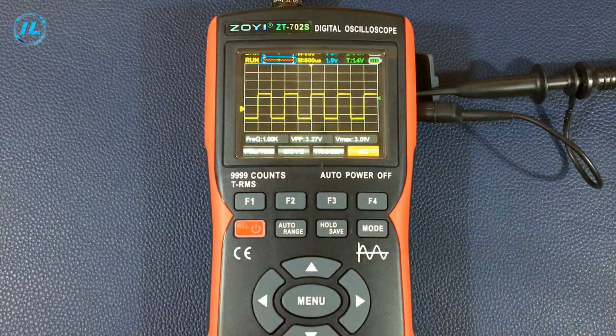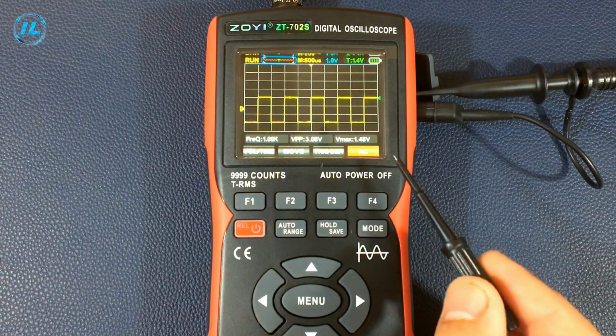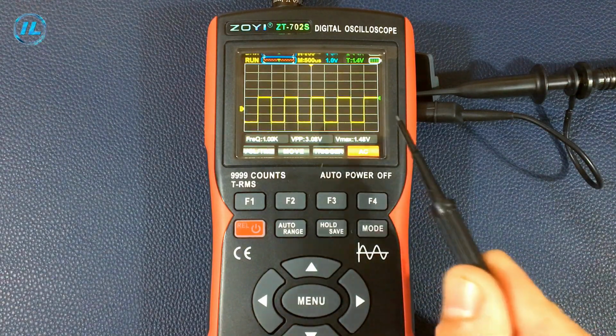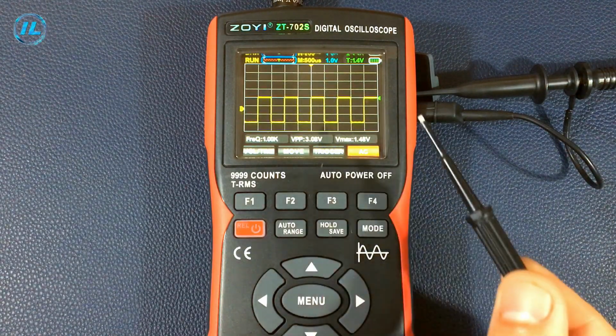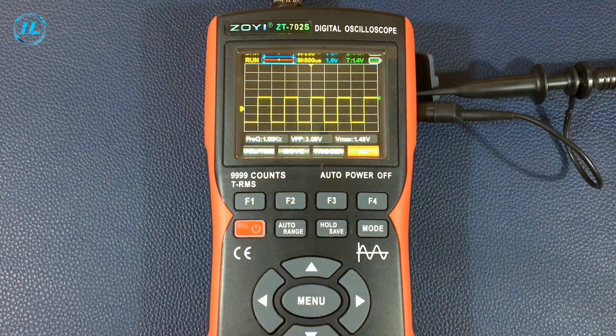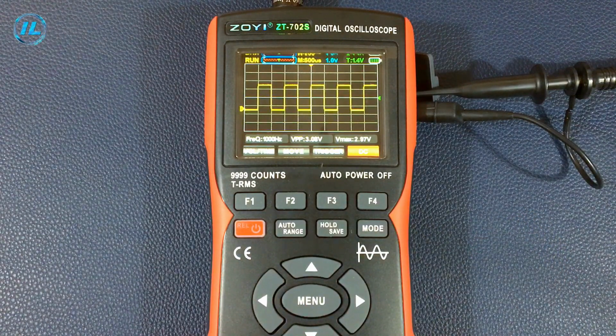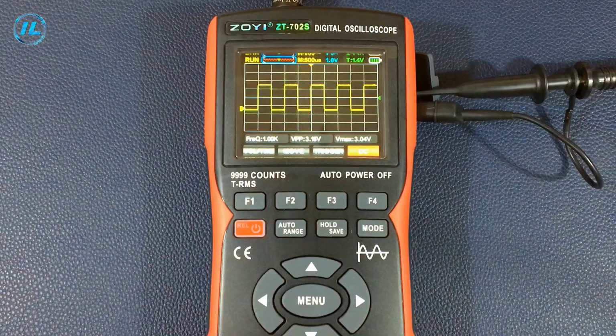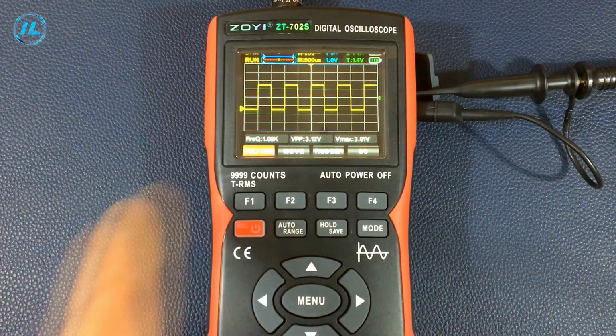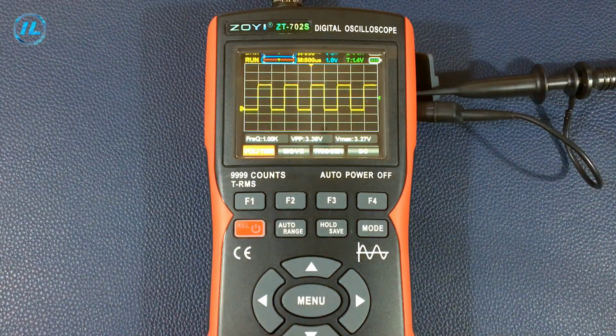The F4 button is the operating mode of the oscilloscope input, that is, open or closed input. AC mode is a closed input, that is, the alternating voltage is displayed on the waveform, and the constant component is cut off by a capacitor at the input. DC mode means open input. In this case, the oscilloscope shows both the alternating voltage and the constant component of the signal. These are the main 4 functional features of the ZT702S oscilloscope, but there are additional ones.